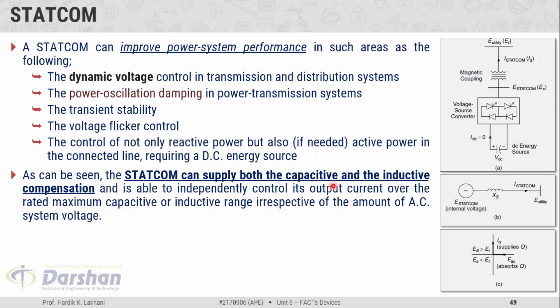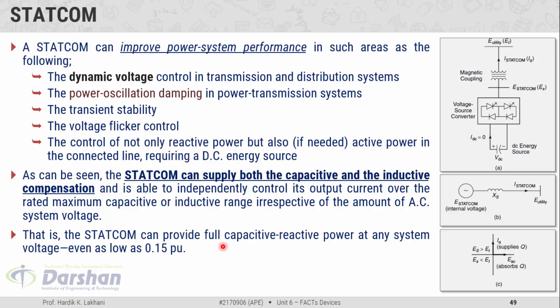The STATCOM can supply both capacitive and inductive compensation — it can absorb reactive power as well as inject reactive power into the system. Notably, the STATCOM can provide full capacitive reactive power at any system voltage, even as low as 0.15 per unit. This will be described further with the help of the VI characteristic when comparing STATCOM and SVC.